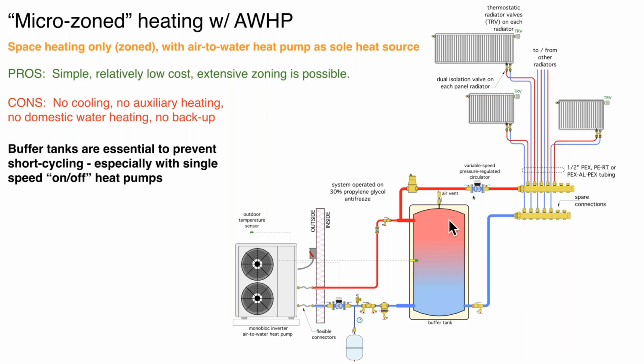And from the buffer tank, you'll see here's a small variable speed pressure regulated circulator. There's dozens of products on the market from all the major manufacturers for that. And then over on the right, panel radiators on home run circuits. Now, this system design, just the way it's shown, there's many zones. And I'm showing a few panel radiators, but you could easily have 10 or 12 panel radiators. And what we don't want to do is create a situation where one panel radiator is calling for heat, and we're turning on a heat pump that has a heating output perhaps 10 times greater than what that panel radiator requires. That's why the buffer tank is there. Okay, we have to stabilize the rate of heat production with the rate of heat transfer to the load.